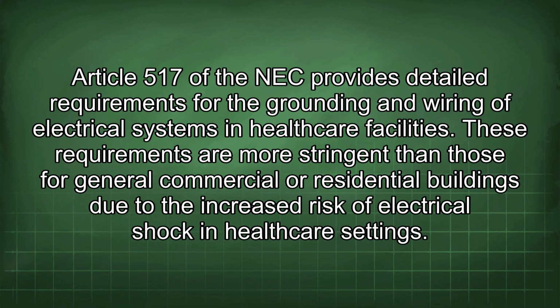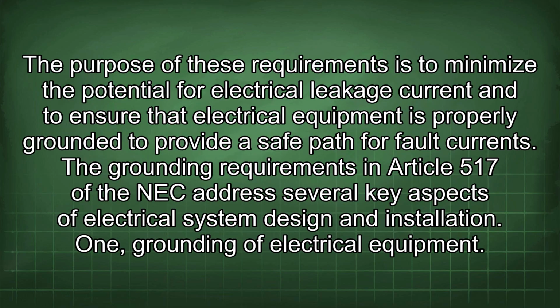Article 517 of the NEC provides detailed requirements for the grounding and wiring of electrical systems in healthcare facilities. These requirements are more stringent than those for general commercial or residential buildings due to the increased risk of electrical shock in healthcare settings. The purpose of these requirements is to minimize the potential for electrical leakage current and to ensure that electrical equipment is properly grounded to provide a safe path for fault currents.